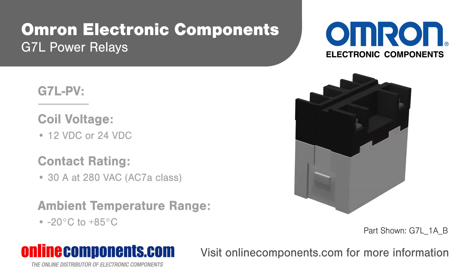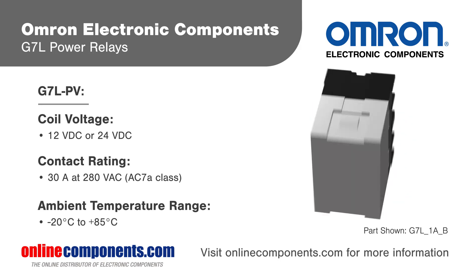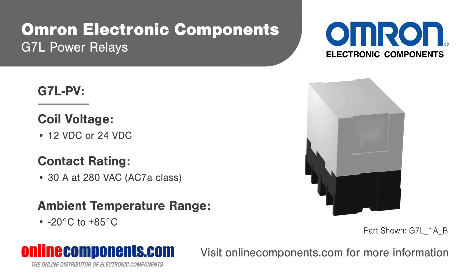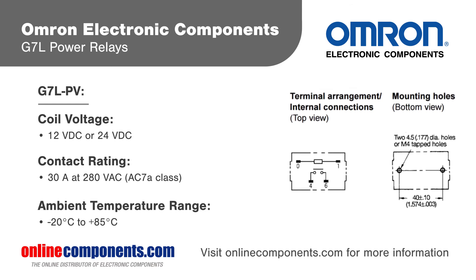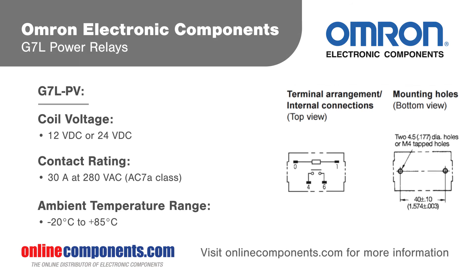The G7LPV variant is designed specifically for inverters and photovoltaic power systems and features contacts rated for 30 amps at 280 volts AC and a higher max ambient temperature of positive 85 degrees Celsius. G7LPV relays also lower power consumption by more than 85% by reducing coil voltage after relay operation.